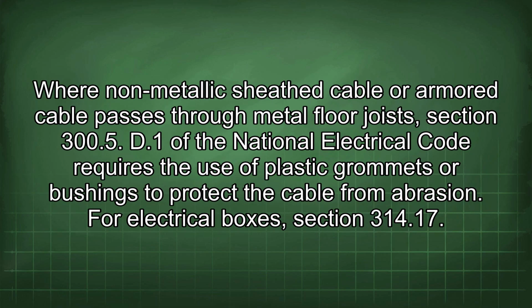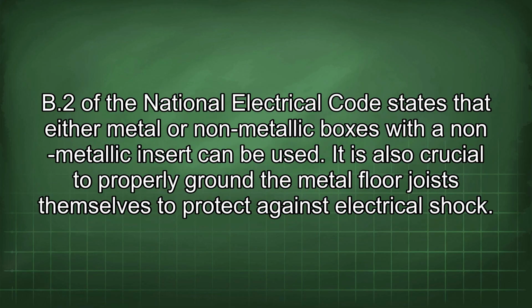Where non-metallic sheathed cable or armored cable passes through metal floor joists, Section 300.5 D1 of the National Electrical Code requires the use of plastic grommets or bushings to protect the cable from abrasion. For electrical boxes, Section 314.17 B2 of the National Electrical Code states that either metal or non-metallic boxes with a non-metallic insert can be used. It is also crucial to properly ground the metal floor joists themselves to protect against electrical shock.